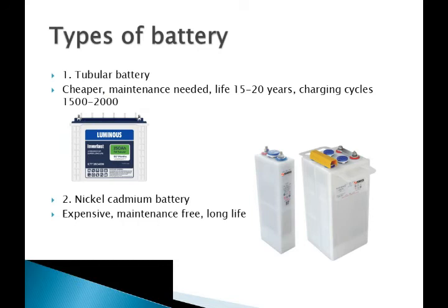There are two types of batteries available in the market. The first one is the tubular battery and the second one is the nickel cadmium battery. The tubular battery is cheaper compared to the nickel cadmium battery. Tubular batteries require maintenance, with a life cycle of 15 to 20 years and a charging cycle of 1000 to 1500. The nickel cadmium battery is expensive but offers good performance and requires no maintenance.